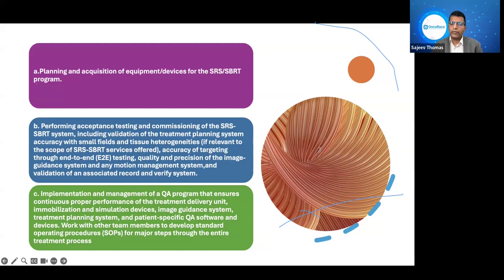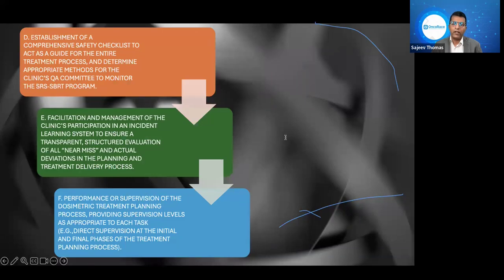So system commissioning involves performing the acceptance testing and commissioning, including validation of the treatment planning system, accuracy of targeting, image-guided systems, and record and verify systems, and implementing and managing a QA program to ensure the continuous proper performance of the treatment delivery and immobilization and simulation devices, image guidance systems, treatment planning systems, and patient-specific QA software devices from the very beginning of the program. It is also important to establish a comprehensive safety checklist for the entire treatment process. It also involves the incident learning system: facilitate and manage the clinic's participation in the incident learning system to evaluate deviations in planning or treatment delivery.